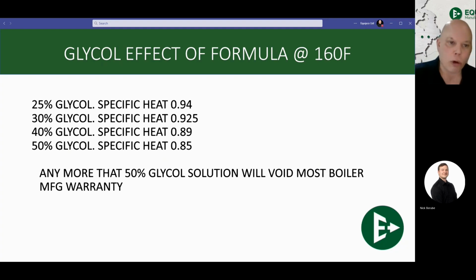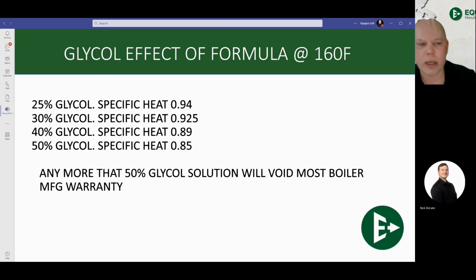So we need to oversize our pumps and oversize our boilers to get where we need to go. At a 50% glycol solution, we have decreased the efficacy by 15% right off the top. So that 100,000 BTU boiler is only going to be giving you 85,000 BTUs. You can't move that extra 15,000 BTUs through it because the glycol solution will not carry any more heat than that. Specific heat plays by the rules of physics. Pretty hard to argue with physics. It's just the way it is. So the most efficient way to move heat in a hydronic system is 100% water, but we're not crazy. We understand that there are snowmelt systems and reasons for glycol, but these are what you need to know about. The more glycol you add, the less effective a system becomes. Not less efficient, it's still the same efficiency, but less effective. There's a difference there between the heat carrying capacity of these 2 water solutions.